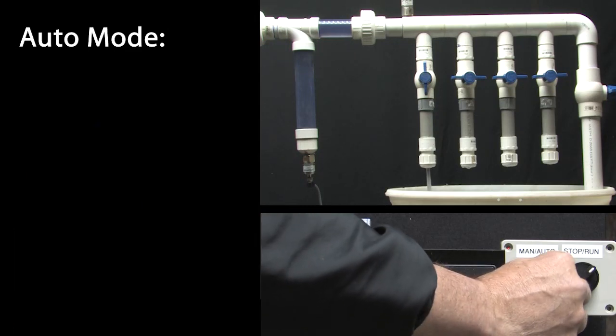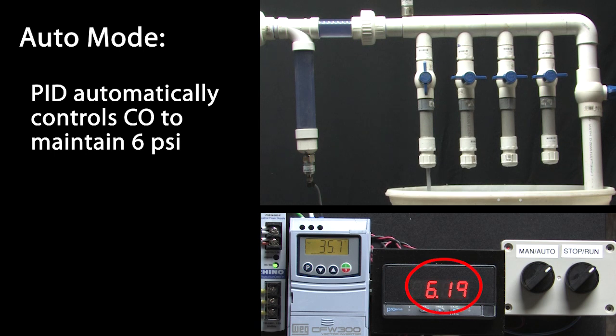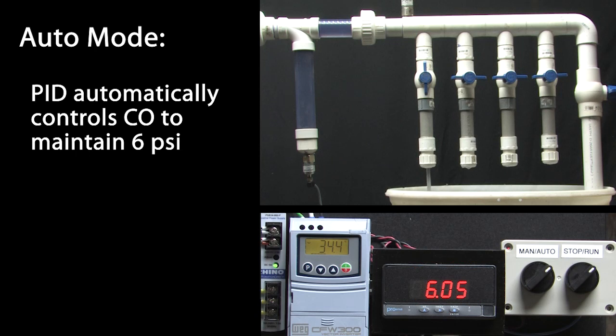Let's flip over to having PID control the output to automatically maintain 6 psi. And sure enough, with one valve open, the system settles out right at 6 psi.